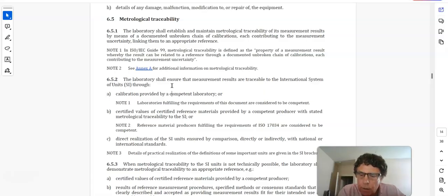But a year later, so this is May 1st, 2024. So May 1st, 2024, Mettler comes out, checks your balance, everything's good, gives you a certificate, it's good for a year. Then they come back May 1st, 2025, and you're in your office, you're the quality manager, and Mettler comes in and says, hey, I'm done. Here's your piece of paper. Here's your calibration certificate. It's all good now. Oh, by the way, when I checked the calibration when I just got here, it was not in calibration, so I adjusted it, but no worries, everything's good now.